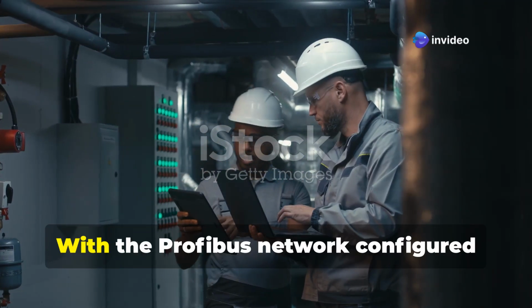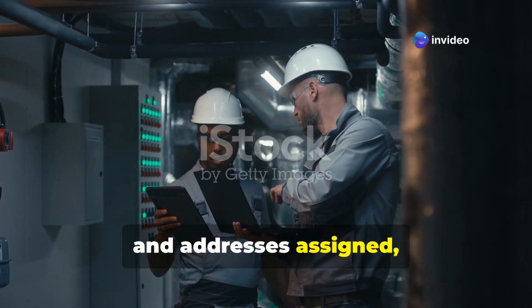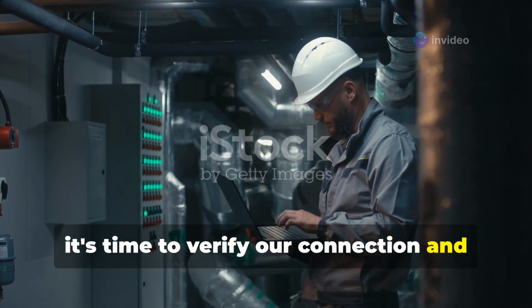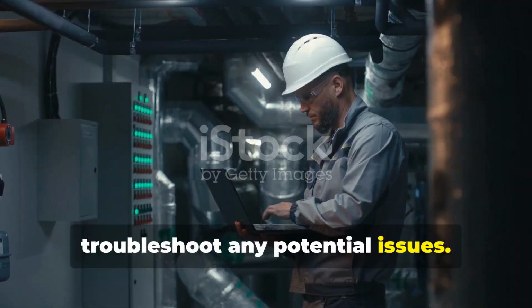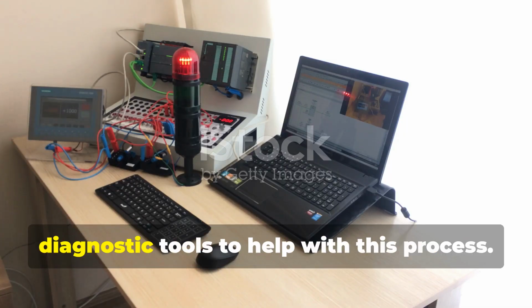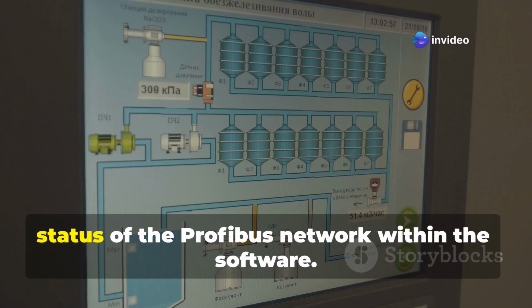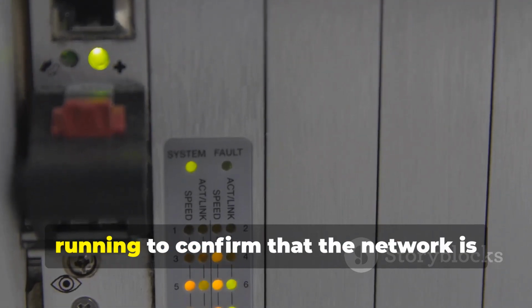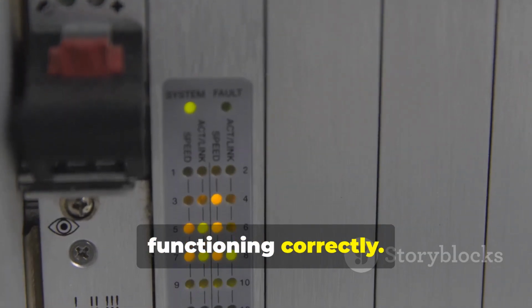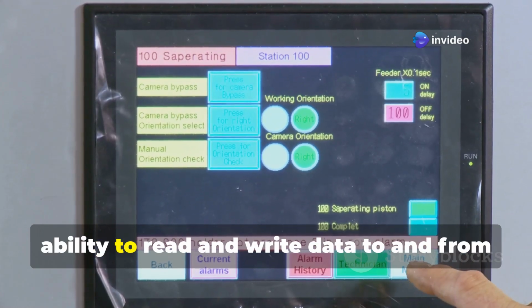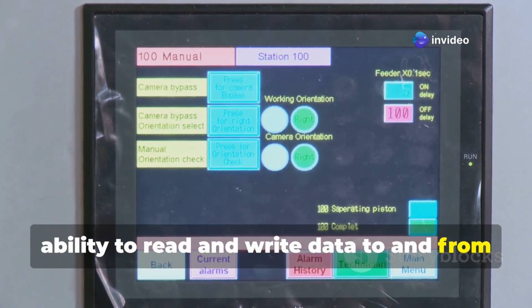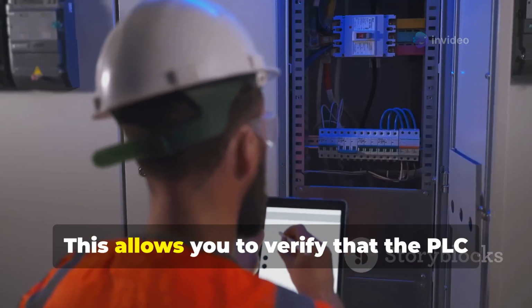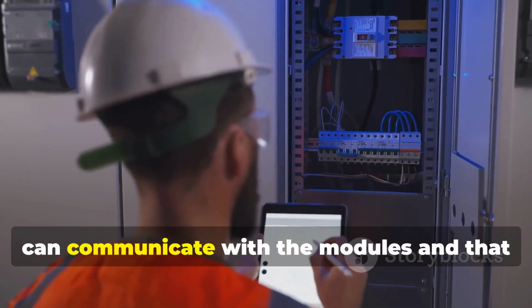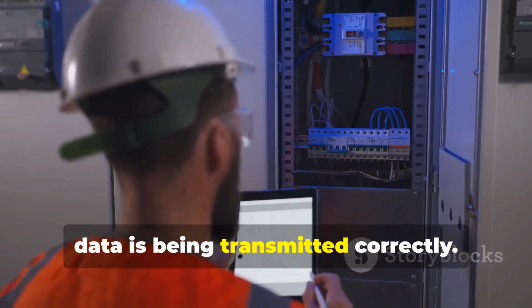With the Profibus network configured and addresses assigned, it's time to verify our connection and troubleshoot any potential issues. Most PLC programming software provides diagnostic tools to help with this process. One common method is to monitor the status of the Profibus network within the software. Look for indicators such as online or running to confirm that the network is functioning correctly. Another useful diagnostic feature is the ability to read and write data to and from the remote I/O modules. This allows you to verify that the PLC can communicate with the modules and that data is being transmitted correctly.